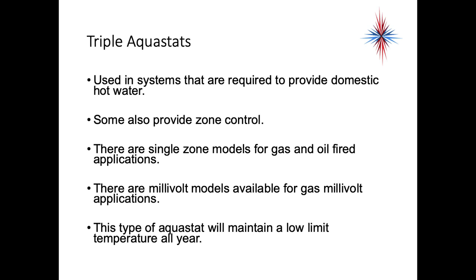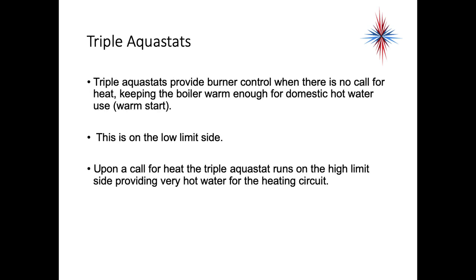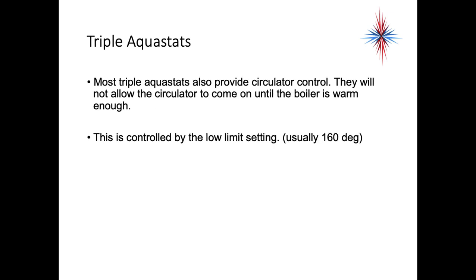Triple aquastats are used in systems required to provide domestic hot water. Some also provide zone control. There are single zone models for gas and oil fired applications, and millivolt models available for gas millivolt applications. This type of aquastat maintains a low limit temperature all year round — the boiler is always warm. Triple aquastats provide burner control when there's no call for heat, keeping the boiler warm enough for domestic hot water — known as warm start. Upon a call for heat, the triple aquastat switches over to the high limit side, providing very hot water for the heating circuit. Most triple aquastats also provide circulator control and will not allow the circulator to come on until the boiler is warm enough, controlled by the low limit setting, usually about 160 degrees.